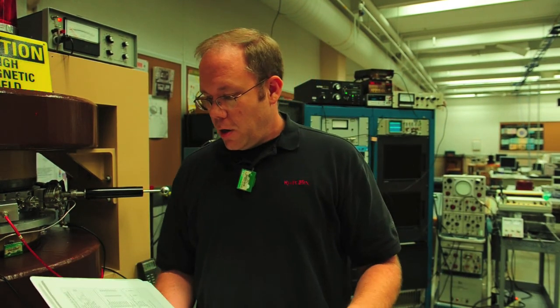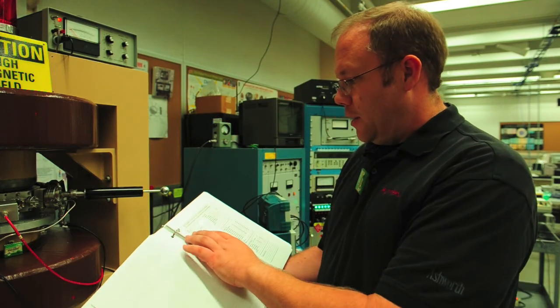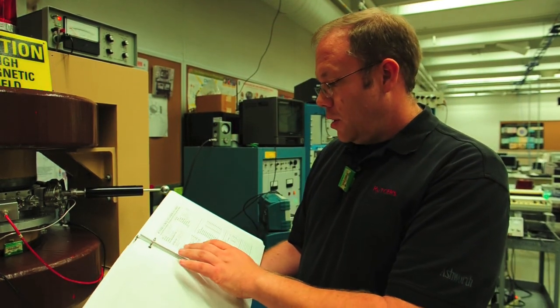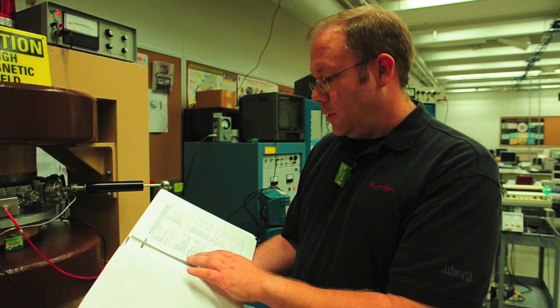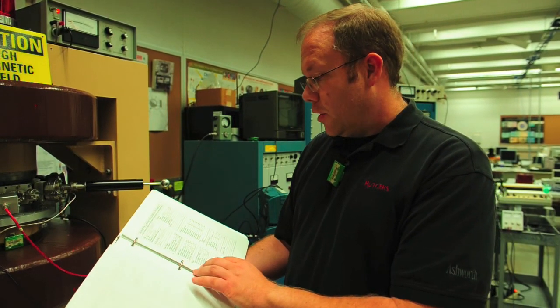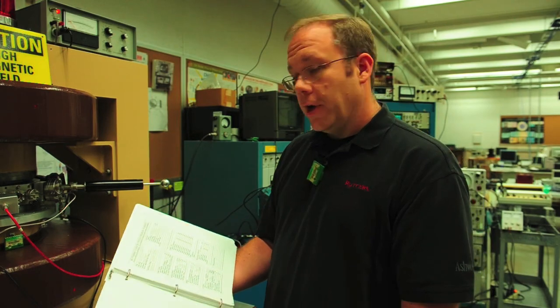We've come back from lunch. All the while, the vacuum system has been pumping out the chamber. And the chamber pressure is in the low minus 6 range, 10 to the minus 6 torr. And that means that's sufficiently good to start operating the cyclotron. All of the atmosphere has been pumped out, all of the contaminants to a good enough degree have been removed, and we can start accelerating protons. But before we do that, we must fill out a daily run log sheet. And this is what we fill out. The date, the operators, brief description of the run, information about the magnet water cooling, the vacuum system, and the RF system. And also that we're accelerating hydrogen.